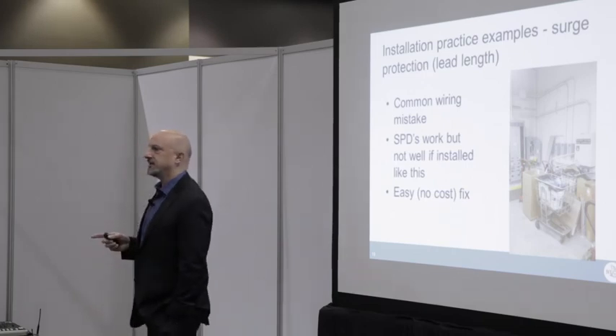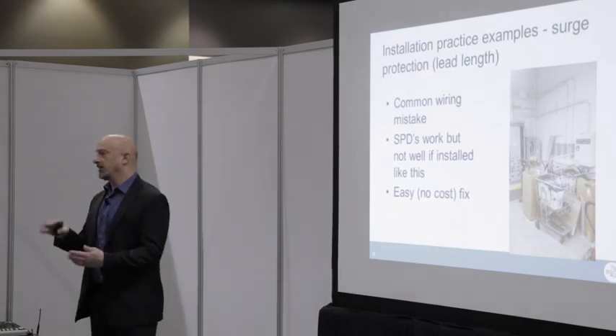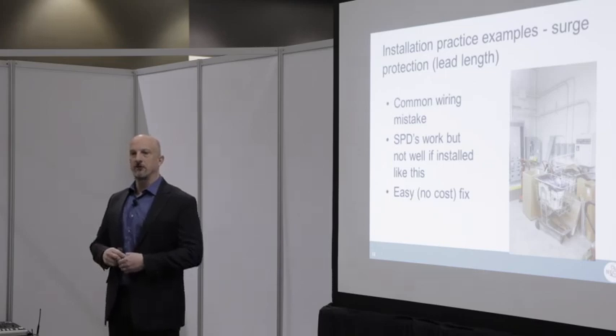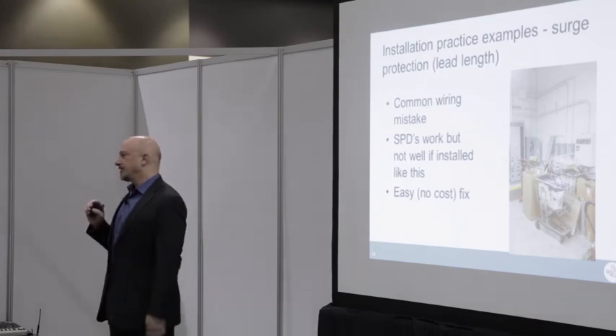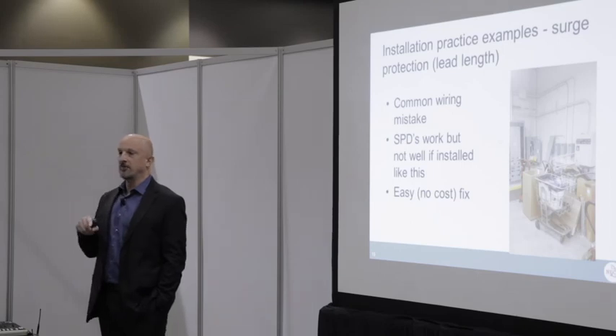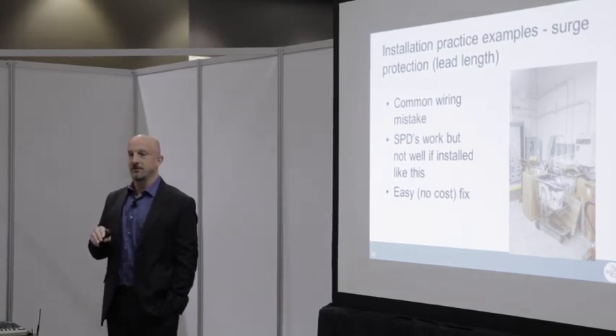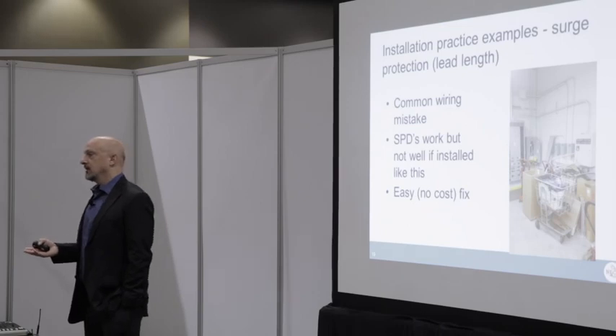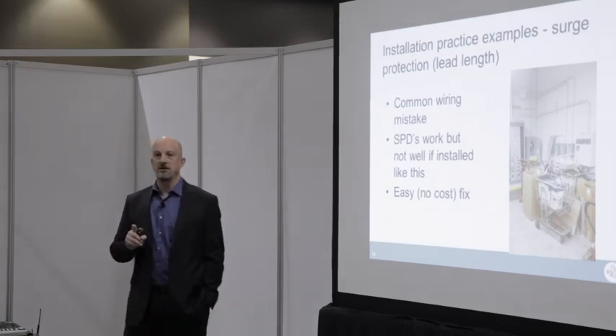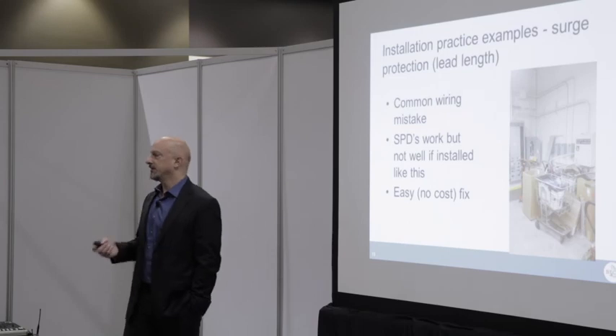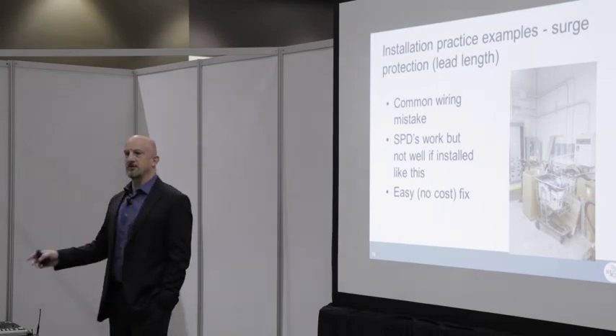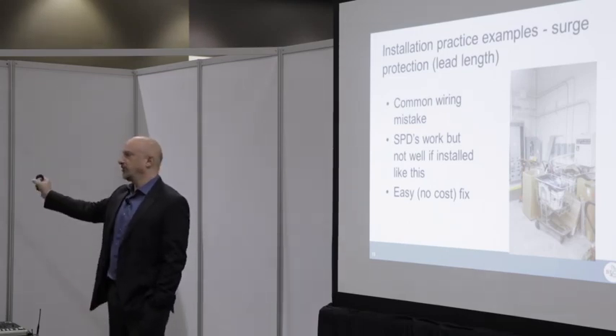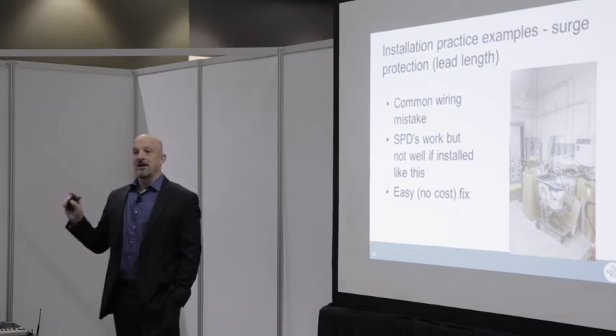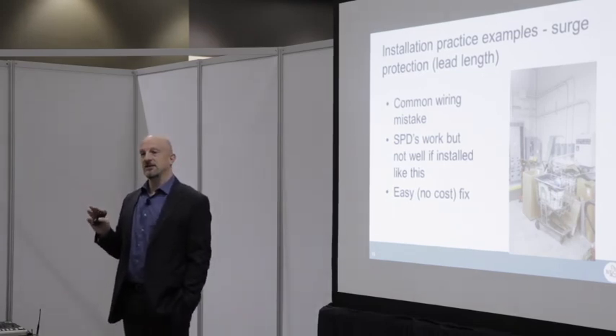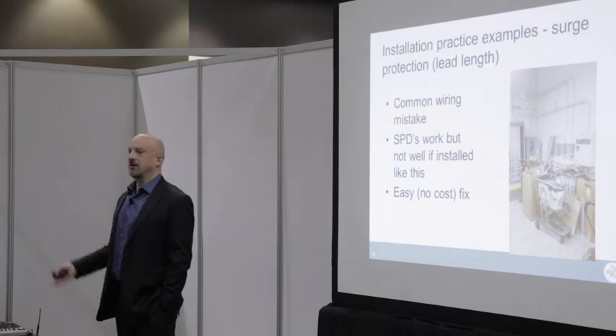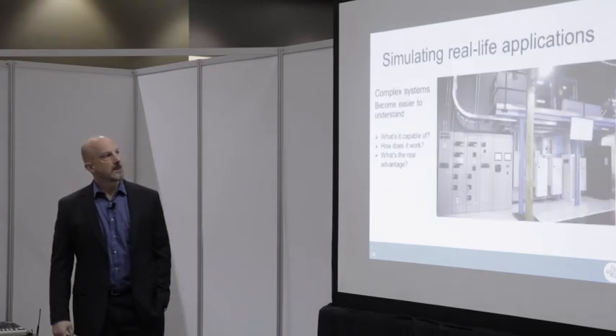A lot of times when people install them, what's the first thing you do right before you turn on the power? They high pot the system, looking for grounded cables and stuff. They turn off the surge protector, because if you high pot the system with the surge protector on, it's going to clamp and burn it up. So you turn it off. You know what they usually forget to do? Turn it back on. So a lot of times they go out and hear, hey, your surge protector's burned out, but really the lights are off and the breaker just needs to be turned on. Again, it's not usually electricians that cause that, but they can be the hero when they find it.